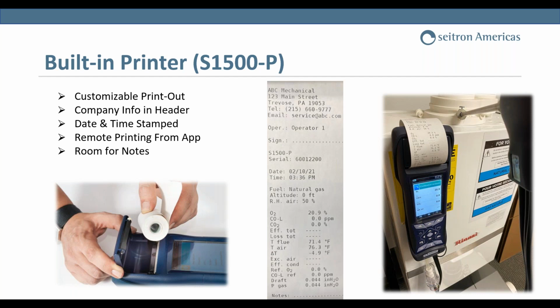This is a huge component because what a lot of customers, and we teach this also in our classes, is that we don't just like selling calibration and service because we like to have the instruments back once a year. And usually whenever we sell an analyzer, sometimes technicians ask, how often do they have to be calibrated? Well, it doesn't matter. You pick any make, brand, or model you want. We recommend an annual calibration because we certify the instrument so that when the technician takes a test, usually if you get into any trouble, the first question that gets asked is, when was the last time that unit was calibrated? Do you have documentation? And that's the documentation, that printout. So that's why we have a spot for the signature, and you can customize it, but that's where that liability concern comes into play.